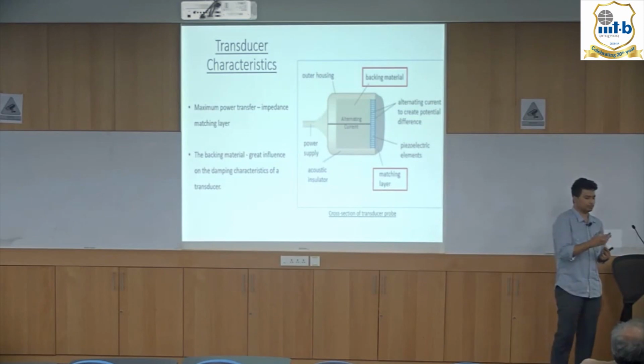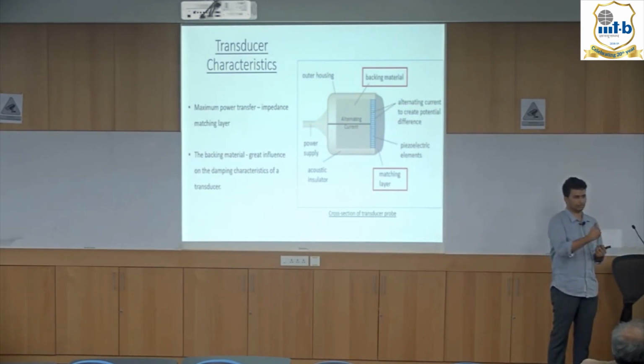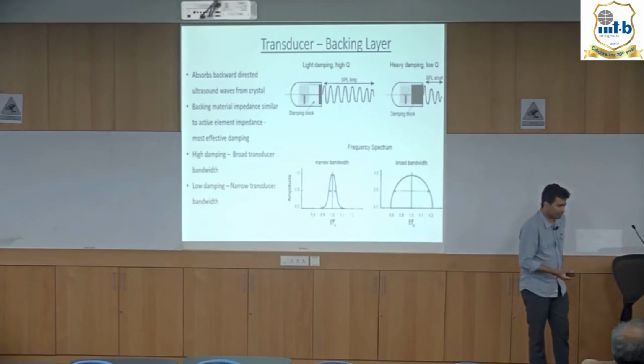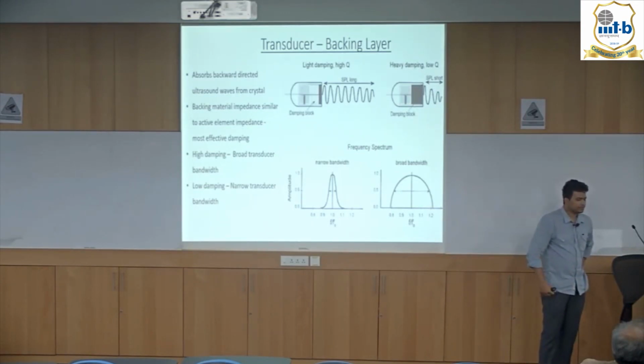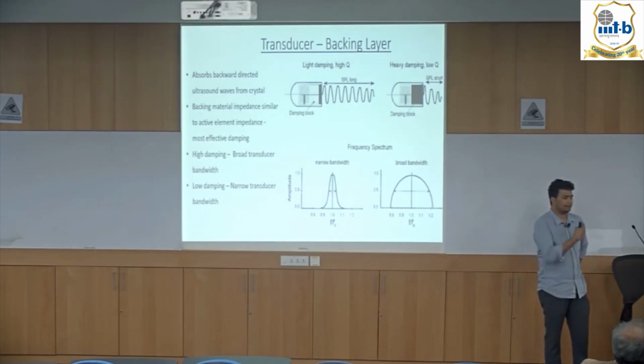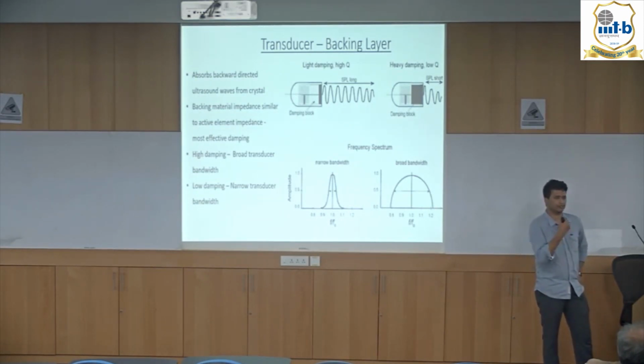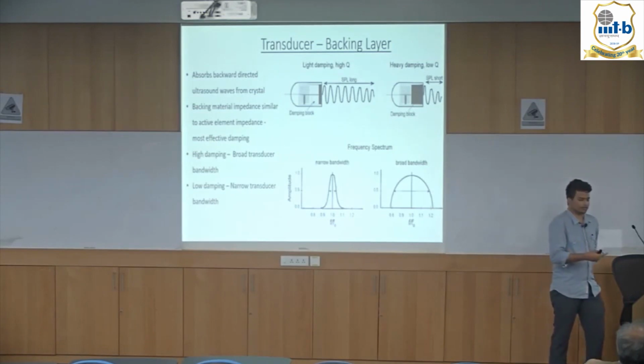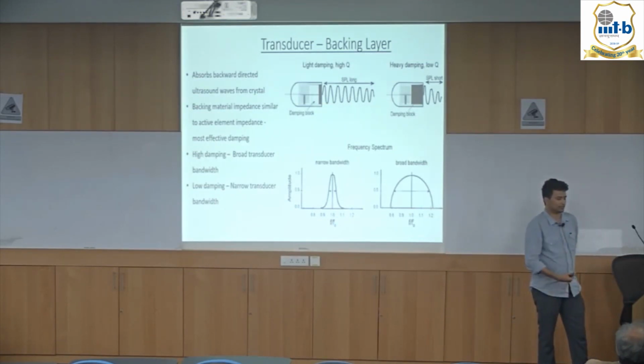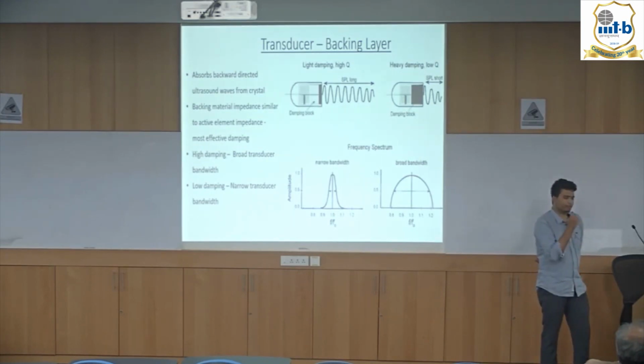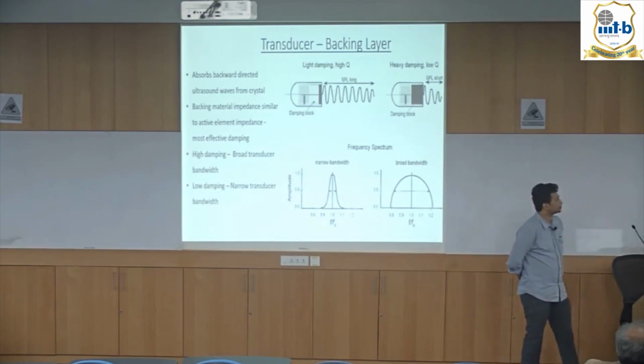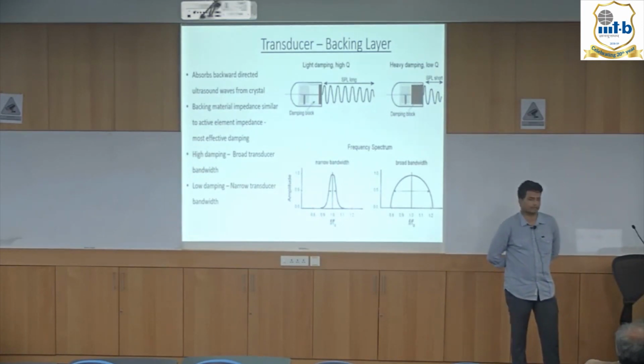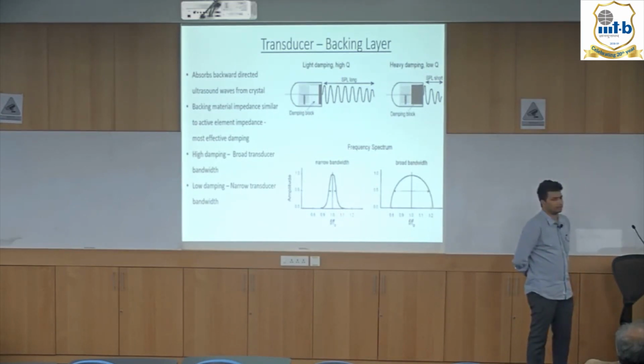To attenuate, or not let, the piezoelectric crystals resonate, there is a damping material called the backing layer. The damping of the backing layer in these transducers is measured using a parameter called the Q factor. Transducers with a high Q factor have backing materials with low damping, and since their damping is low, they have a narrow bandwidth. Similarly, low Q factor transducers have backing material with heavy damping, and they have a broad bandwidth.